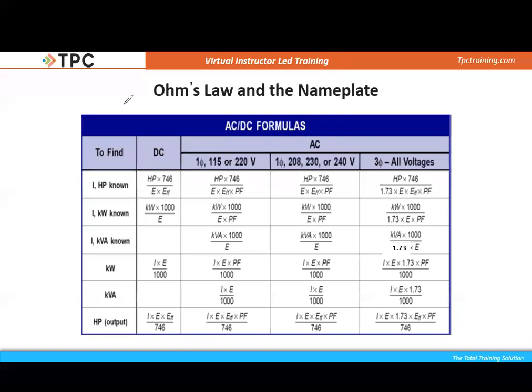Also wanted to talk just a little bit about some of the ways that we can calculate three phase. And so DC, you can see right here, some pretty simple formulas. It looks like we're going kilowatts times 1,000 divided by voltage. I mean, no problem. The minute we get into single phase, though, we have to look at power factor. And I'm going to explain power factor coming up shortly. But let's jump over here to three phase.